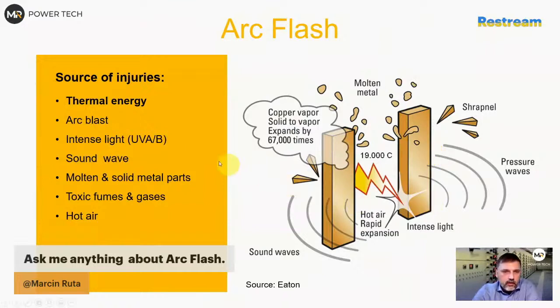That's what we call arc blast. Another topic is that even if you calculate it, and I might write it as a comment here as my opinion, even if you identify the pressure wave, the only thing you can do is limit the time if possible. But if you're at the bottom time, there's nothing really you can do. You can try to limit the current, which on the transformer side, low voltage side, is not that easy.